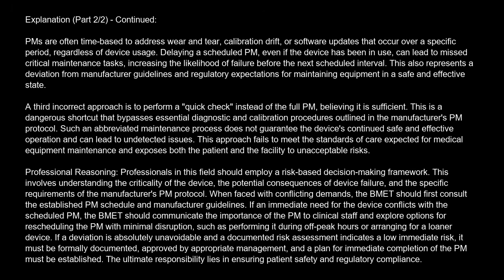A third incorrect approach is to perform a quick check instead of the full PM, believing it is sufficient. This is a dangerous shortcut that bypasses essential diagnostic and calibration procedures outlined in the manufacturer's PM protocol. Such an abbreviated maintenance process does not guarantee the device's continued safe and effective operation and can lead to undetected issues. This approach fails to meet the standards of care expected for medical equipment maintenance and exposes both the patient and the facility to unacceptable risks.